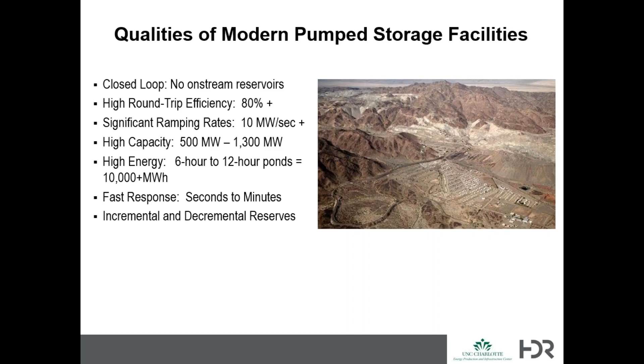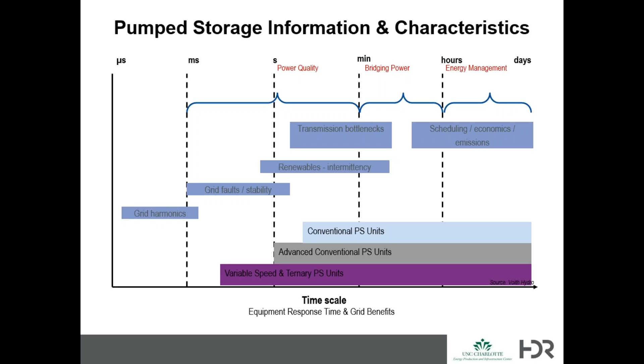There's a perspective that only batteries can provide millisecond and microsecond frequency regulation and grid reliability. This is what existing machines can do today. Here's power quality. This is time. This is energy management, shifting energy from least value to higher value. And then you get variable speed machines, which get into microsecond power quality type response. What's new in the technology is going to a full power pump and frequency inverter, so that if you have a 100 megawatt machine, you have a 100 megawatt power frequency converter, and you have almost unlimited operational flexibility.